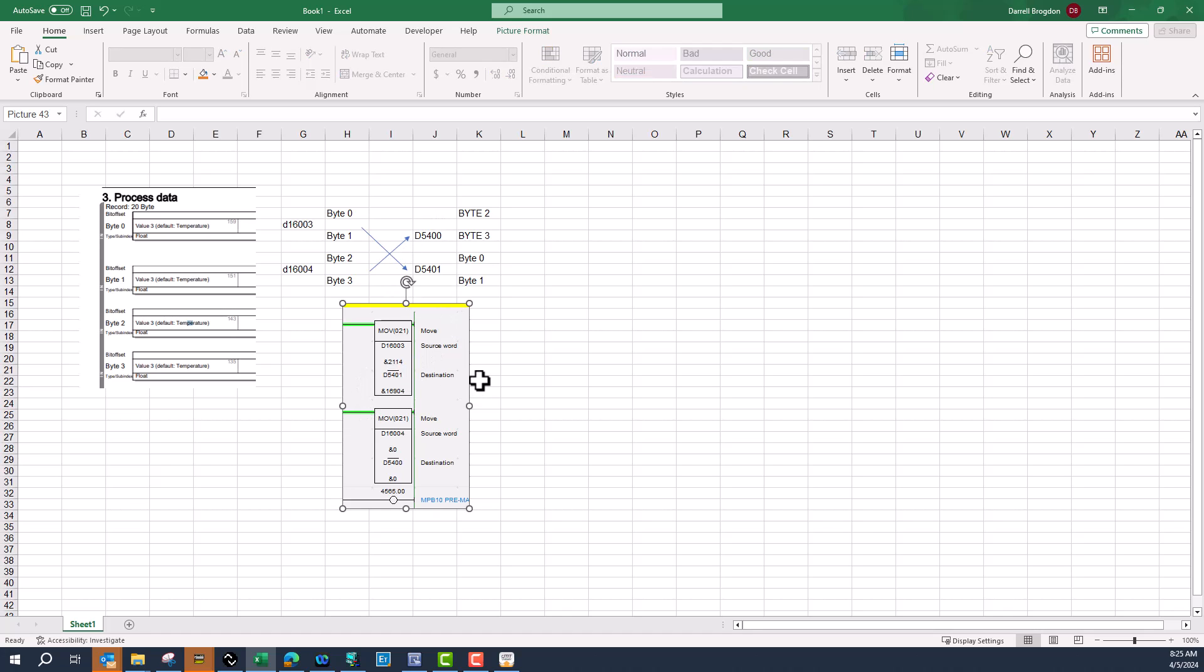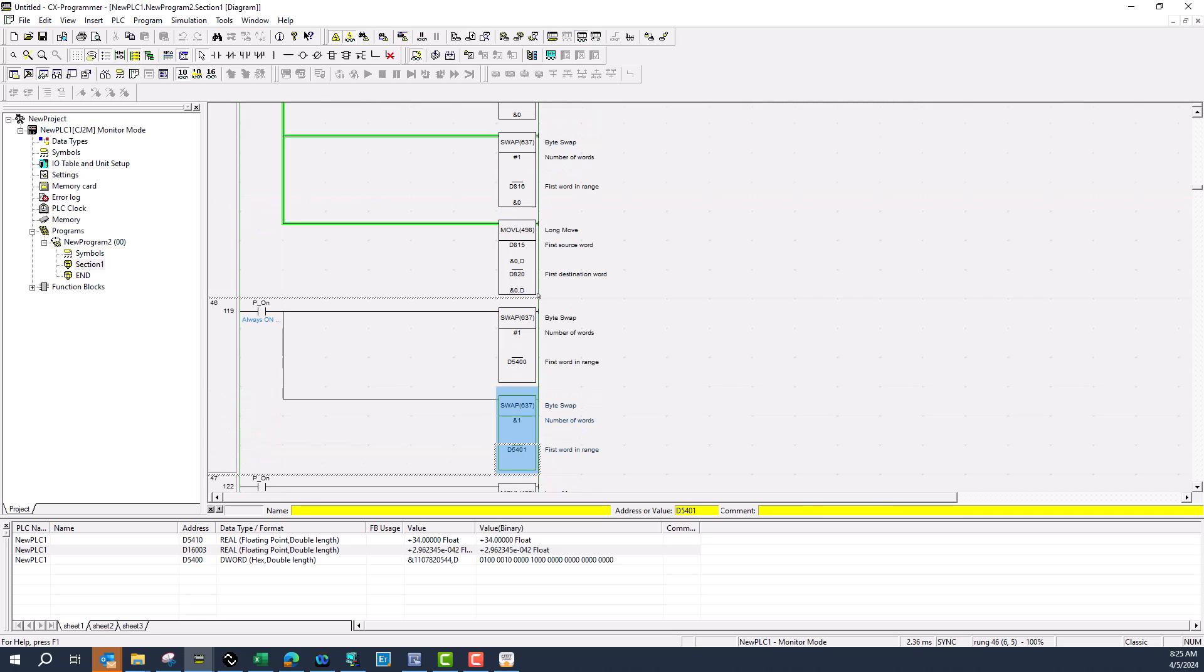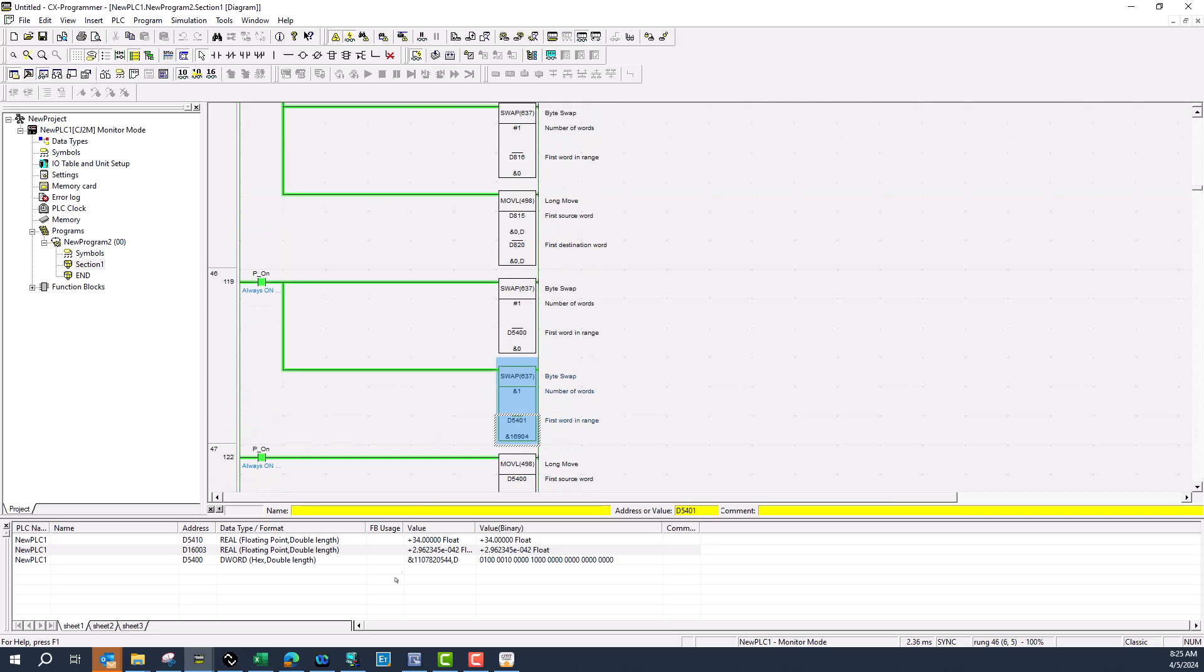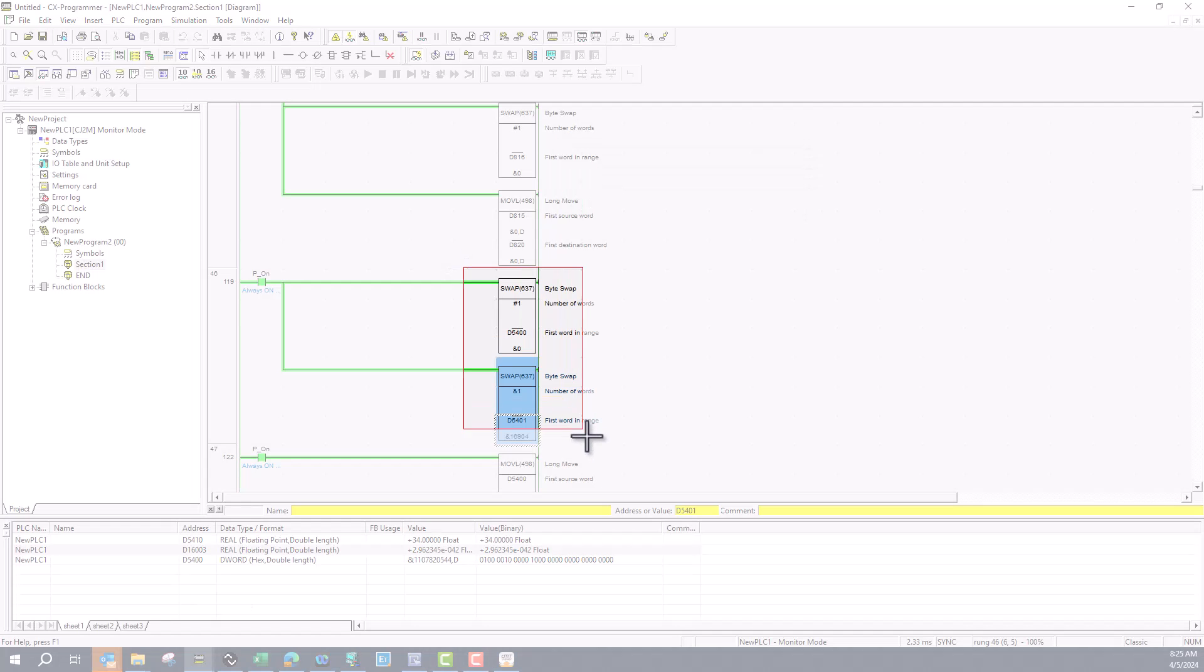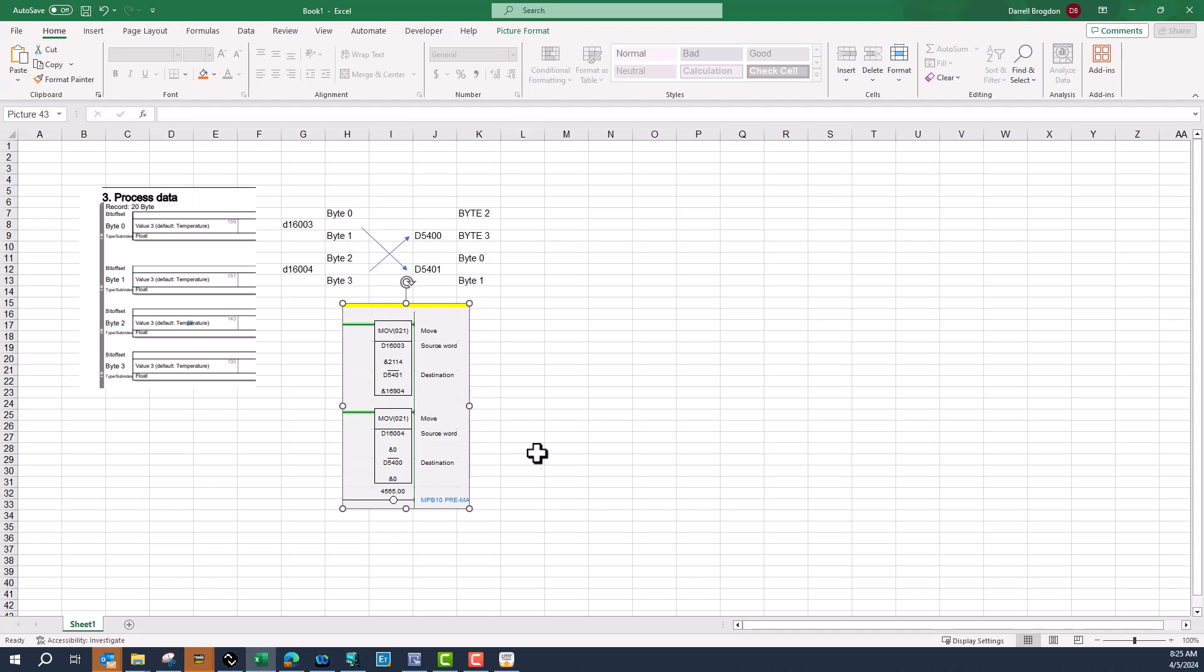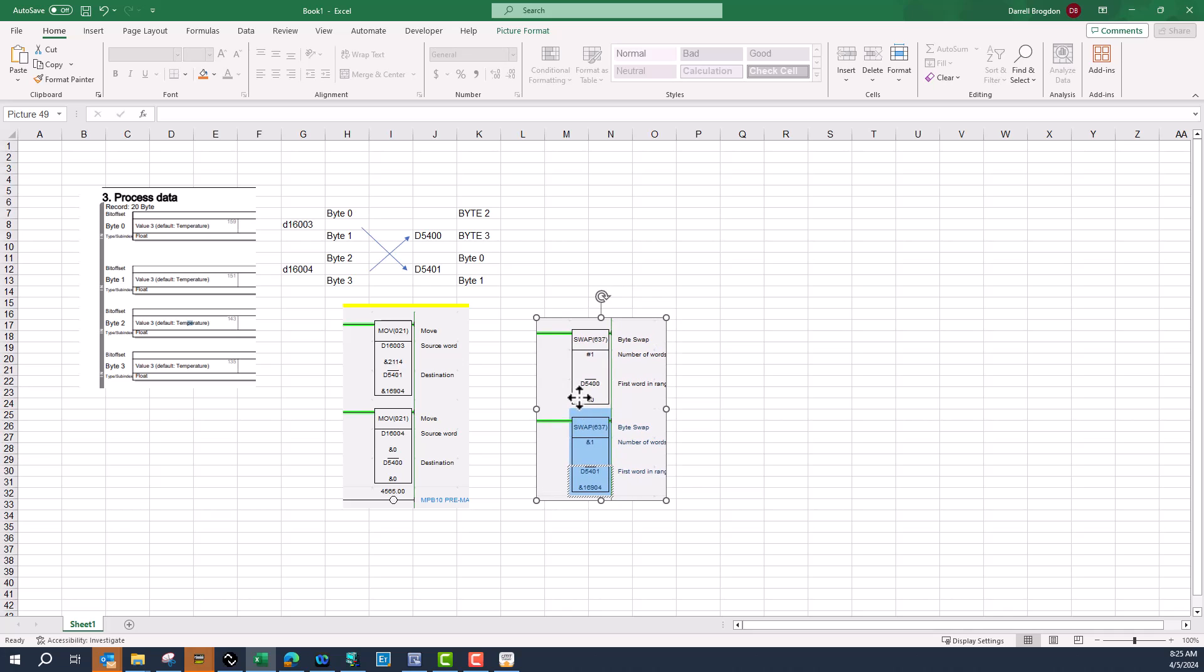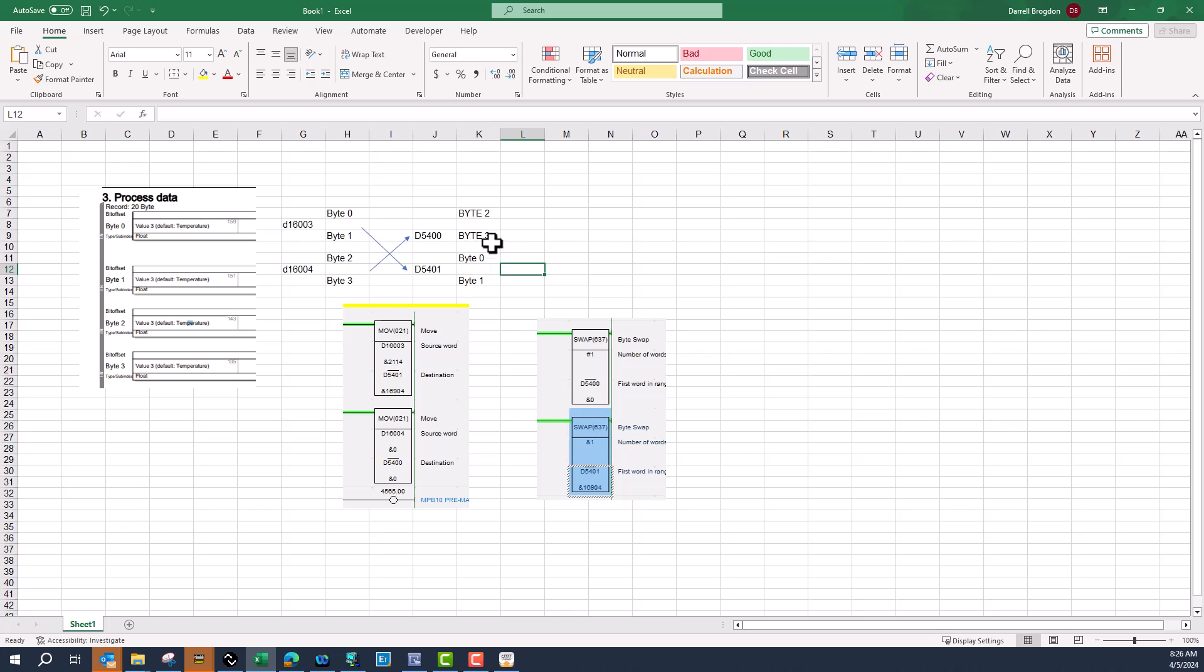Now what we need to do is a byte swap so that I can move the data where it needs to be. You'll see that done in the PLC here using the swap instruction. Once I run the swap, now it's going to swap these two bytes and these two bytes.